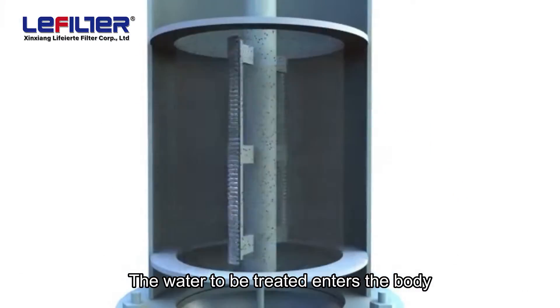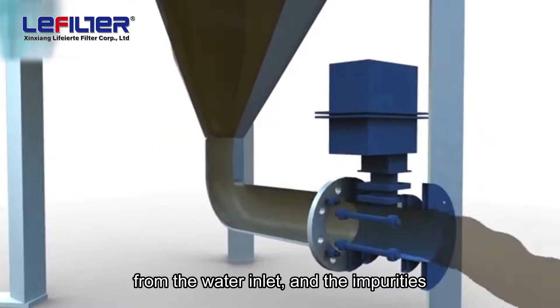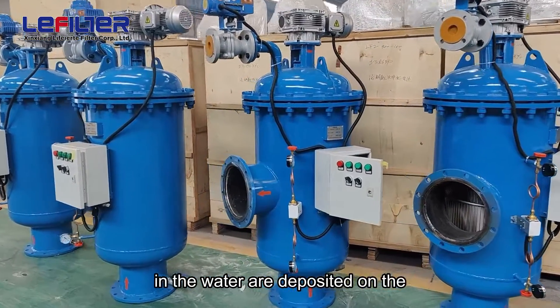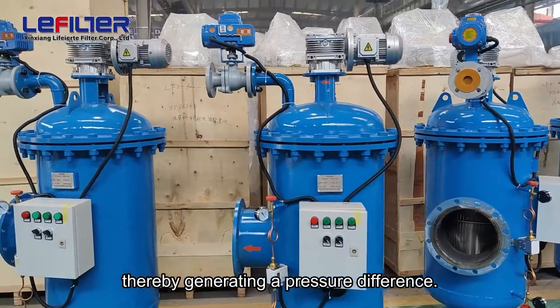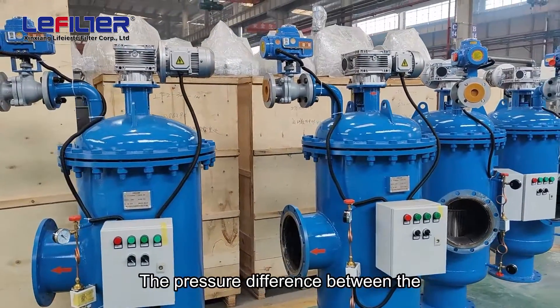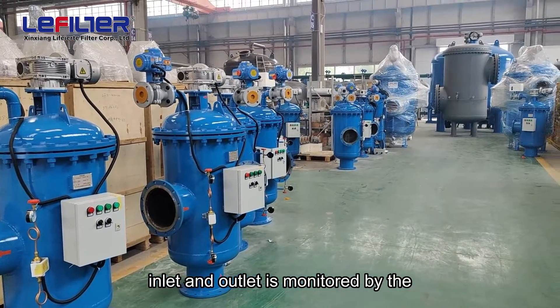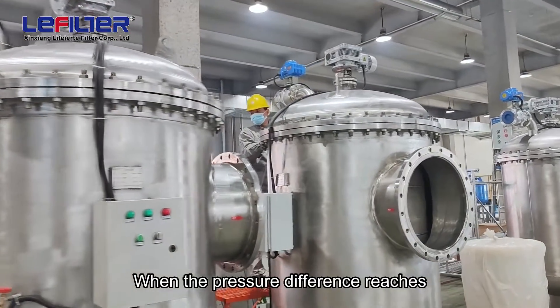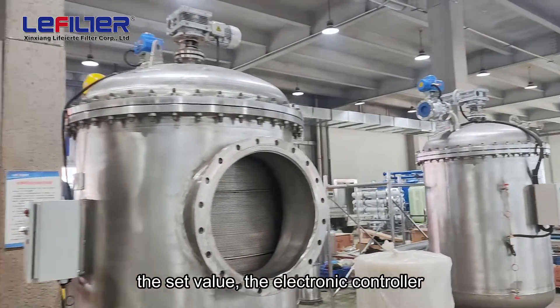The water to be treated enters the body from the water inlet, and the impurities in the water are deposited on the stainless steel wedge-shaped mesh, thereby generating a pressure difference. The pressure difference between the inlet and outlet is monitored by the differential pressure switch.